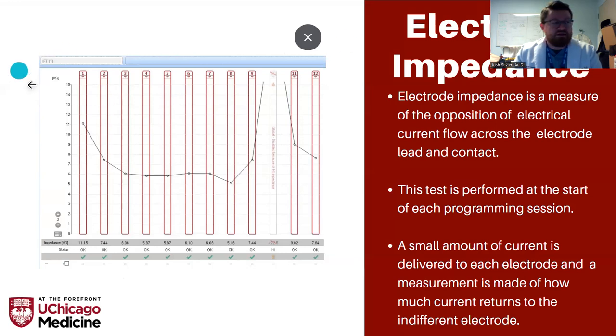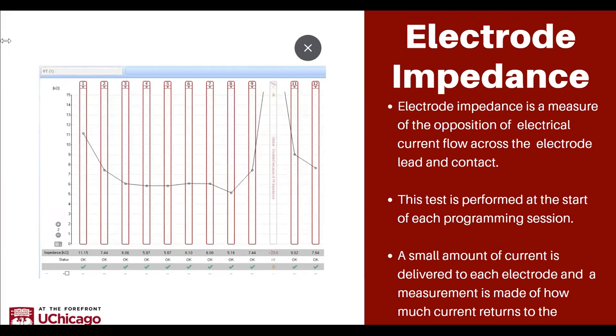Starting off, let's talk about electrode impedances. It is a measure of the opposition of electrical current flow across electrode contact points. A good way of looking at this is how well the electrodes are sitting in a fluid space. It's important to keep in mind that you can have good impedances and the electrode array not actually be in the cochlea. But when it is properly inserted, it can tell us how well that electrode contact is making its stimulation contact with the area around the basilar membrane.